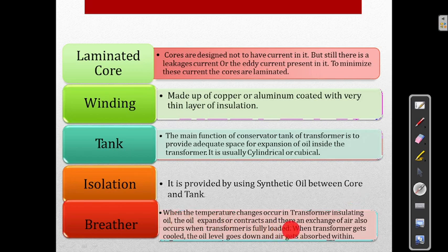When temperature changes occur in the transformer insulating oil, the oil expands or contracts and there is an exchange of air when the transformer is fully loaded. When the transformer gets cooled, the oil level goes down and air gets absorbed within.